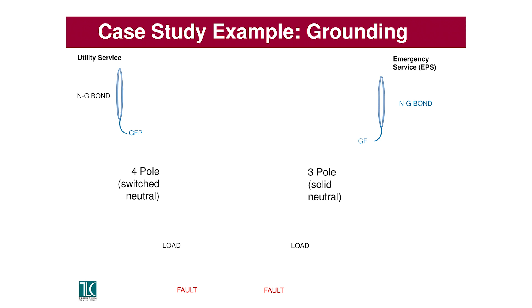And this is a really fancy chart I drew on the plane coming here because I couldn't find a graph that really represented what I wanted to show. And just real briefly, we're showing a sample of a 4-pole switch and a 3-pole switch. So what we're really just representing is what the neutral conductor does. In the 4-pole switch, it's switched, and in the 3-pole, it's not. This really has to do with getting ground fault protection to work properly. When there is a fault, we want the ground faults to flow where we want them to flow so that the ground fault protection can see all of the fault and actually trip the way it's supposed to.